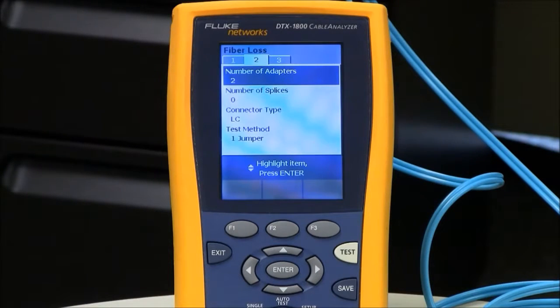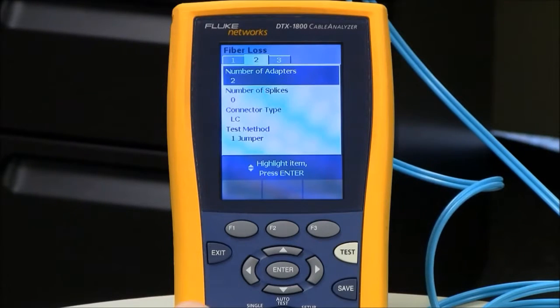My number of splices is 0, even though I'm using mechanical connectors today. When I say mechanical connectors, I'm talking about types such as the Unicam, which have a mechanical splice inside. That's part of the connector. You do not add an extra splice count in there for each of those connectors. My connector type is LC. That's not going to affect the outcome of the test result. That's just going to affect the help screens on the DTX cable analyzer.